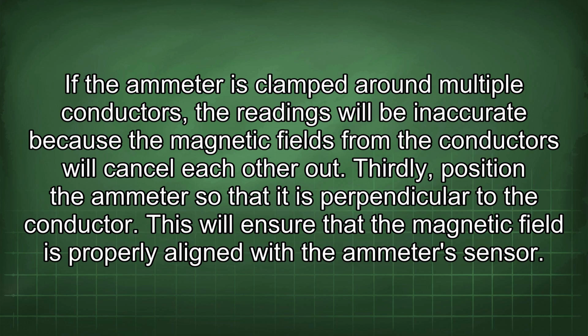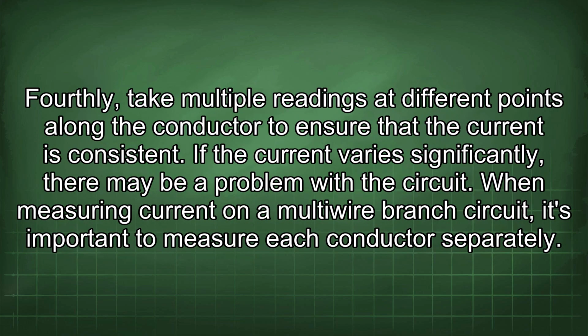Thirdly, position the ammeter so that it is perpendicular to the conductor. This will ensure that the magnetic field is properly aligned with the ammeter sensor. Fourthly, take multiple readings at different points along the conductor to ensure that the current is consistent. If the current varies significantly, there may be a problem with the circuit.